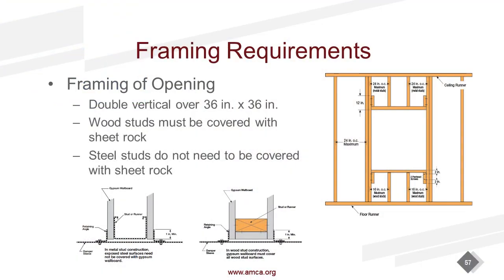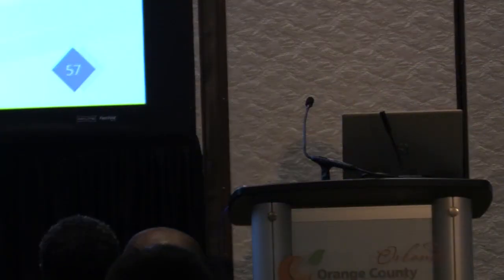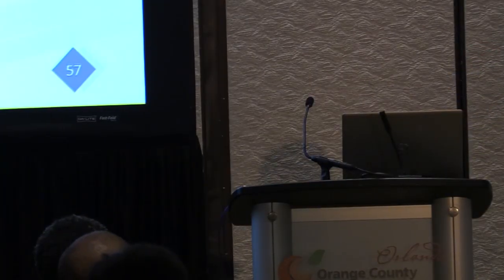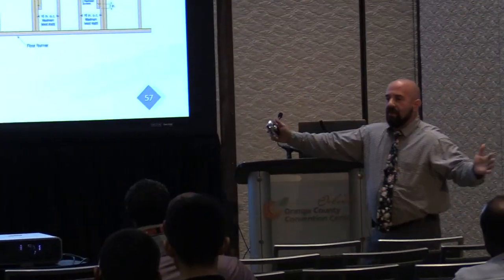Framing requirements are outlined in our manual. It is not the intent of the damper manufacturer to tell you how to build your barrier. It's our intent to tell you how to support and install the damper. So if you put a damper right here and we frame it perfectly and everything's good, and then right next to it you have a 5-foot hole. Is that damper installed properly? Sure, but that barrier's got a giant hole. That's not my problem. Let's put a dashed line around my damper. I can't tell you how to build the barrier.